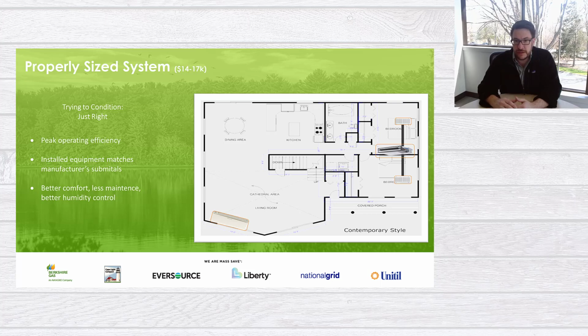Here's a great way to do it. For the large open area, you're putting in a ductless mini split, maybe 12,000 BTUs. Then for the 2 small bedrooms in the back, just put in a ducted unit and drop 2 registers down to each room, with 2 returns for each room so everything stays balanced. You could even have a 3rd register going into the bathroom, so that space is also properly conditioned. That system could be a 6,000 BTU unit, and 12,000 plus 6,000 equals 18,000.